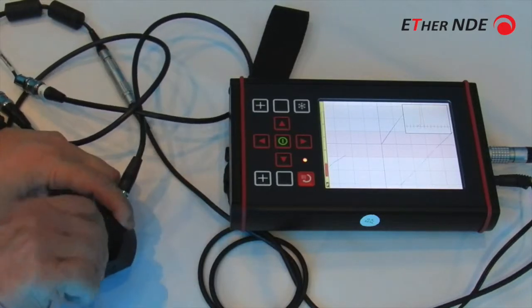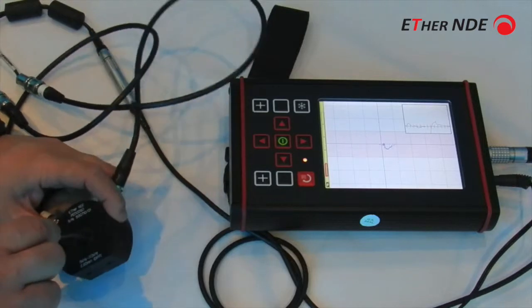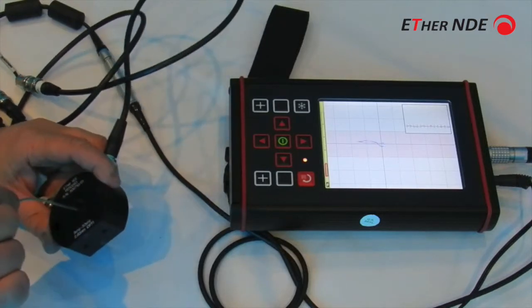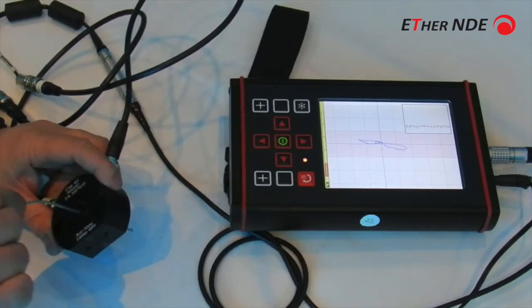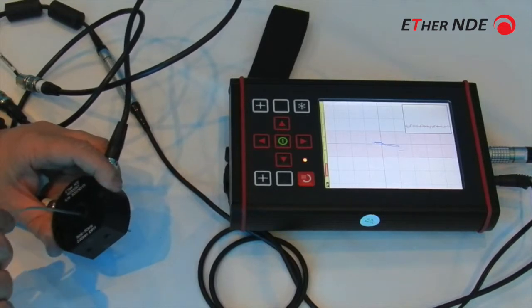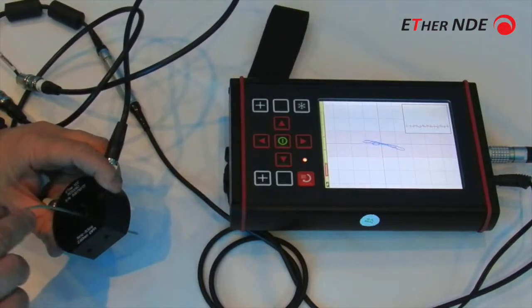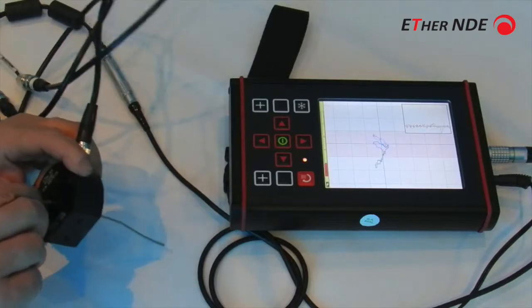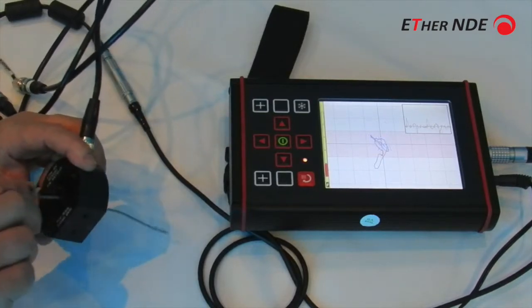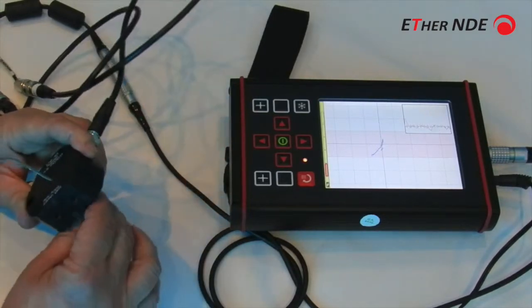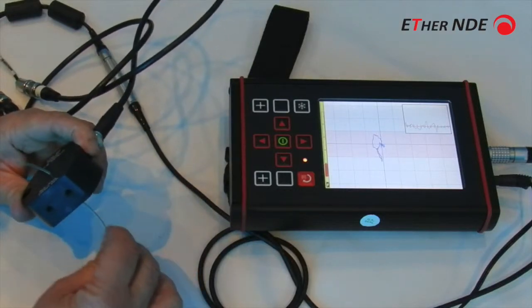And what you've got here is a time-based display, that's the end of the wire going in, so we go through the wire. I've set the noise that comes from the surface, which is caused by the braiding itself, horizontally, and then we get a defect, and that gives a kick on the display, and then keep going up, there's another one up here.